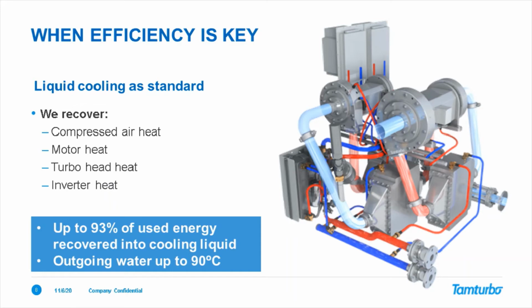And the other thing is that the outgoing water can be up to 90 degrees Celsius, which means that customers using our compressor can really utilize this 70, 80, 90 degree water in their production. Whereas for the legacy technologies, the amount of heat in the water is less, and the temperature of the water is typically much less.